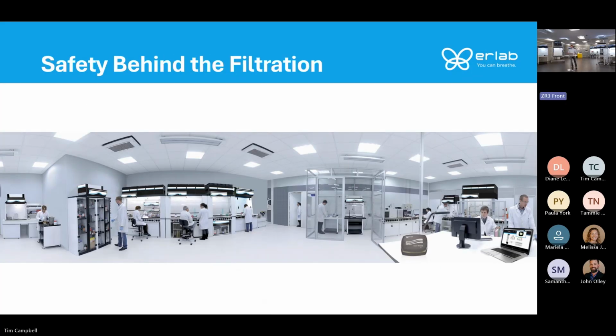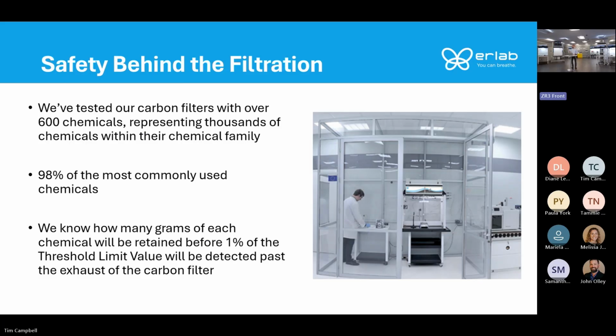Now, how do we know it works? Well, as I said, we invented the first ductless fume hood over 50 years ago, so we have almost 60 years of testing data. This is actually a picture of our R&D center in France. In this picture, you see we have all the ductless fume hoods there. There's no ductwork. We use them for our own research. But there is a glass testing chamber, and in this chamber is where we test the design of our carbon filter shell and our carbon recipe. And we've tested over 600 chemicals with each of our carbon filters. Those 600 chemicals represent thousands of chemical families and are 98% of the most commonly used chemicals in labs today.